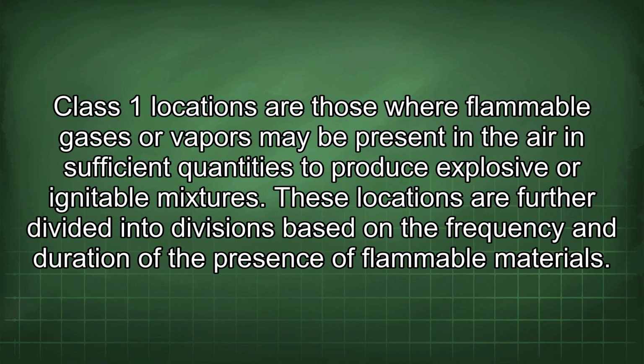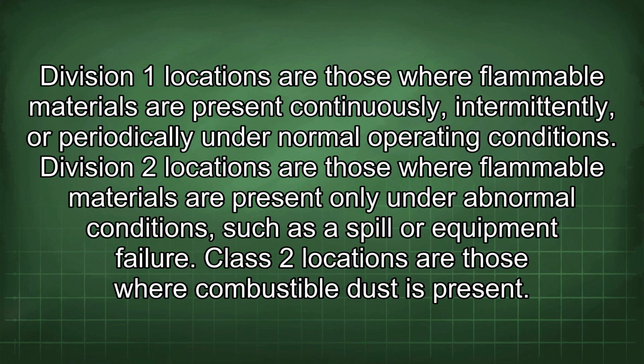Class 1 locations are those where flammable gases or vapors may be present in the air in sufficient quantities to produce explosive or ignitable mixtures. These locations are further divided into divisions based on the frequency and duration of the presence of flammable materials. Division 1 locations are those where flammable materials are present continuously, intermittently, or periodically under normal operating conditions.